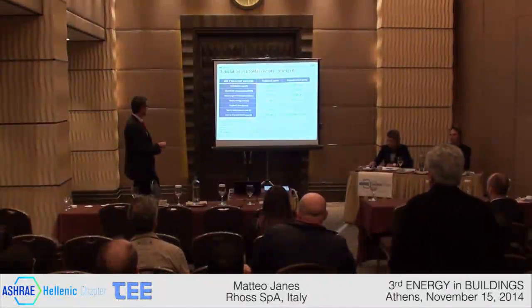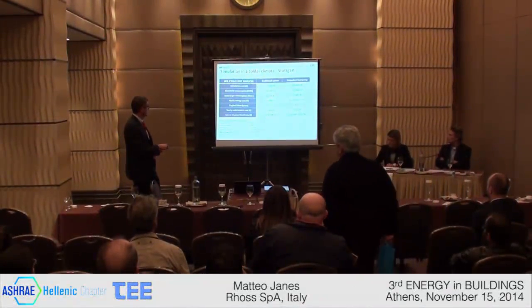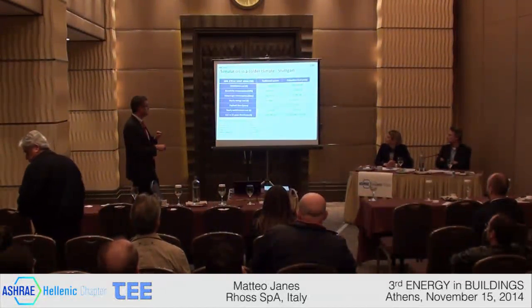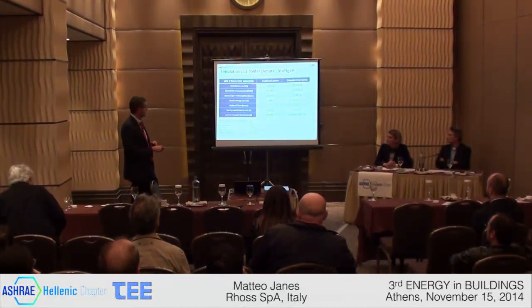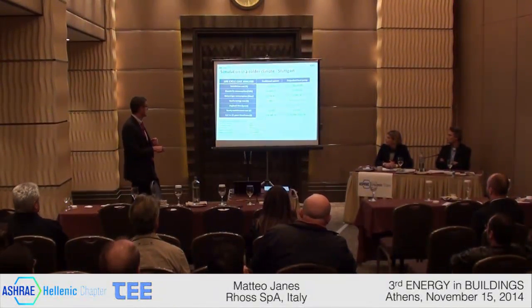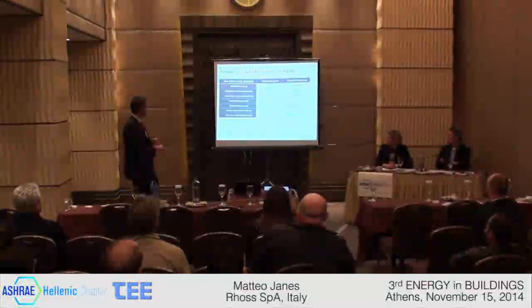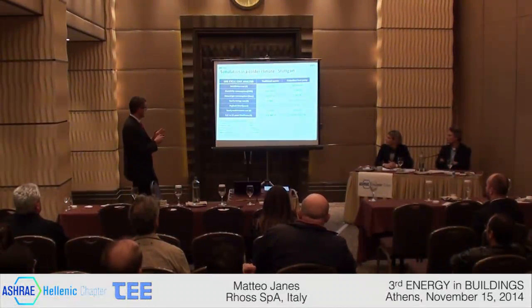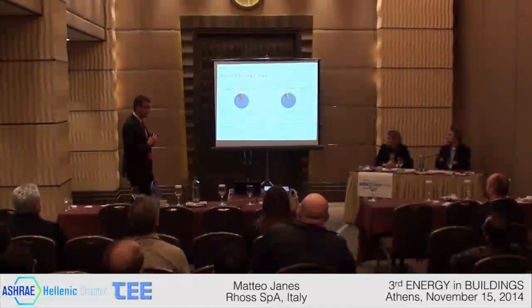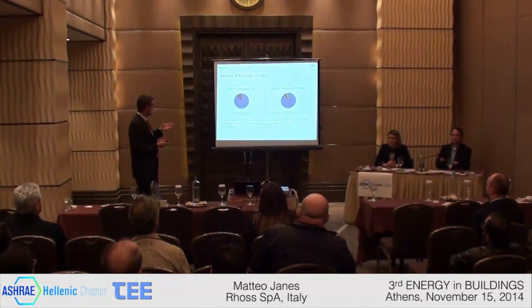But still, considering the operation saving, the yearly energy consumption can be reduced by around 22%, which makes the payback of the unit slightly higher than 2 years. And still, in a 15-year time frame, we can see a life cycle cost reduction of around 17%. The reason for this saving is in this slide.